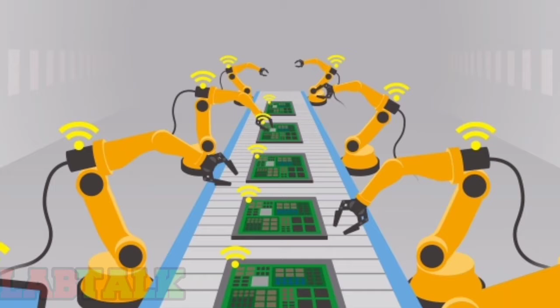DQ, that is design qualification, should ensure that the instrument or system has all the necessary functions and performance criteria that will enable it to be successfully implemented for the intended application and to meet business and regulatory requirements. Design qualification should include first the selection of the technique or type of equipment, description of the intended environment, and description of how the instrument will be used in the selected environment and within a process. If the instrument will be used for several applications, describe a few typical scenarios. Preliminary selection of the supplier, final selection of the equipment and qualification of the supplier and equipment. Discussion and documentation of warranty, familiarization, training, consulting and other vendor services. Development and documentation of final functional and operational specification. Review and approval of user requirement and functional specification by users of the system and by the validation team.